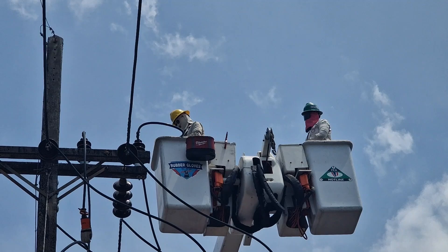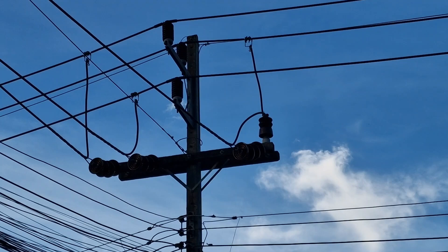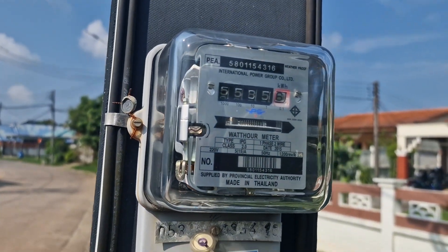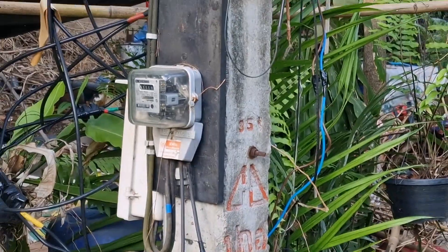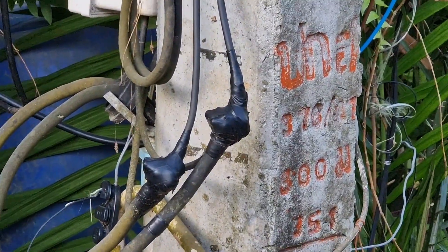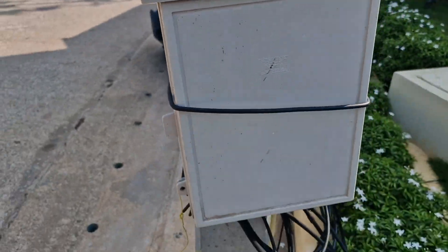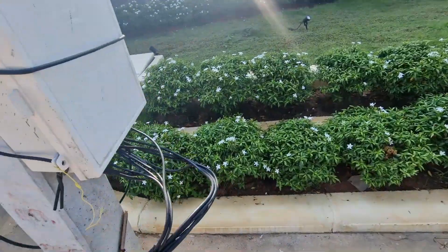Cables chopped and left dangling. HV electricians working on overhead power lines without any protective barriers for the public. 33 kilovolt exposed terminals you can poke with a selfie stick. I'm pretty sure this meter isn't suitably IP rated — and in monsoon season, Thailand gets some pretty f***ing heavy rain. There's so much wrong with some of these installations: undersized cables incorrectly joined without suitable mechanical or environmental protection. Electrical engineering in Thailand seems to mainly consist of connector blocks, tape, and dreams. Electrical boxes secured with discarded wire that can be easily opened by any old Tom, Dick or Ningpu wandering down the street.